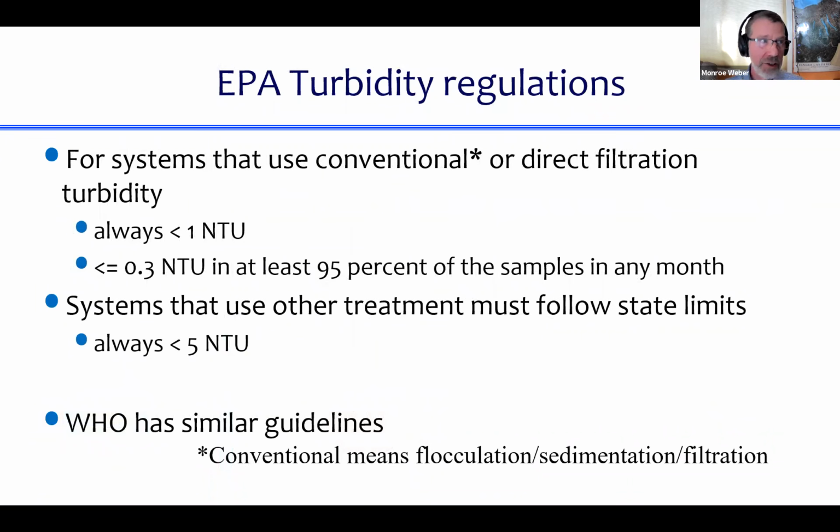The guidelines for how turbid the water can be, isn't it interesting? Turbidity isn't directly in a primary standard. It's just kind of there as like a secondary thought. Like, it's not a microorganism, but it's listed in there along with the microorganisms. And then it becomes what we really focus on, in part because it is so easy to measure turbidity. It costs almost nothing per sample. It's an easy test to run. Just put the sample in, take the measurement, press read on the instrument, or maybe it's reading continuously.